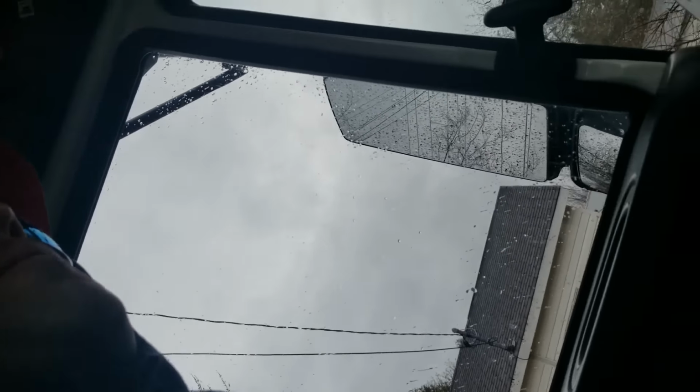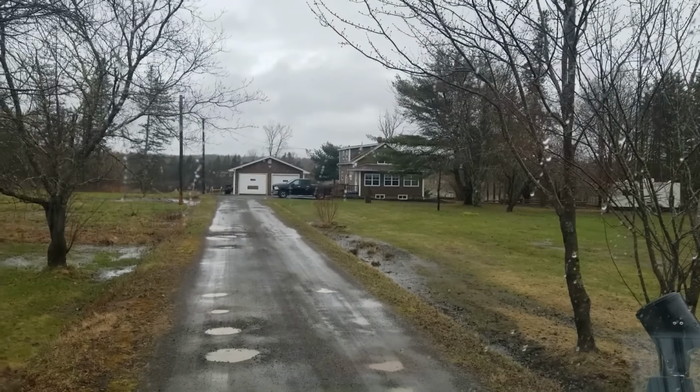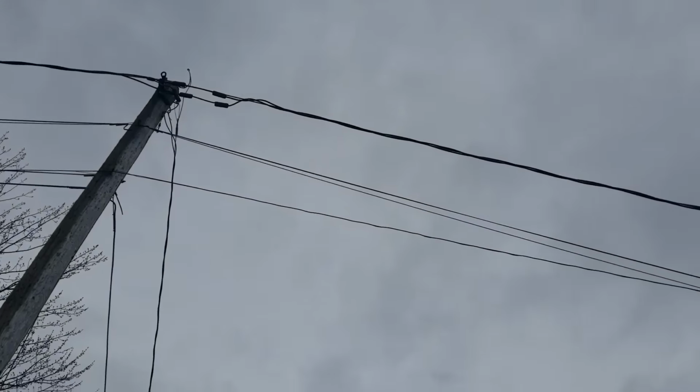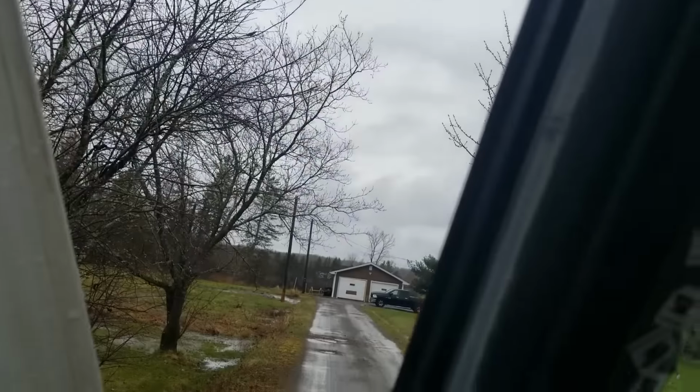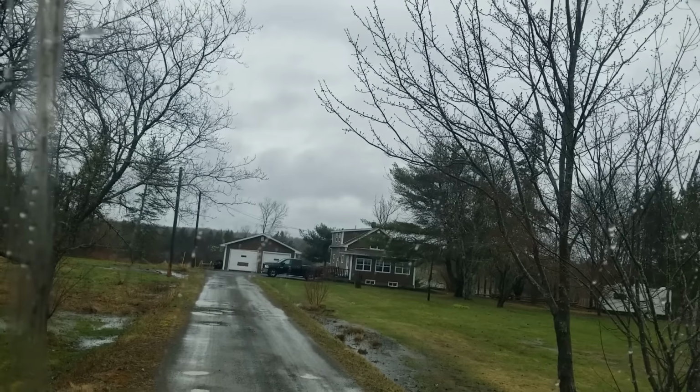Alright, so check it out. I got this call. This house down there has no power. So I went to the meter, no power, both phases. We just went up in the air at this pole here. We checked voltage, 240 volts. A secondary line, 2 more poles. Somewhere between here and here, we didn't only lose one phase, but both phases.